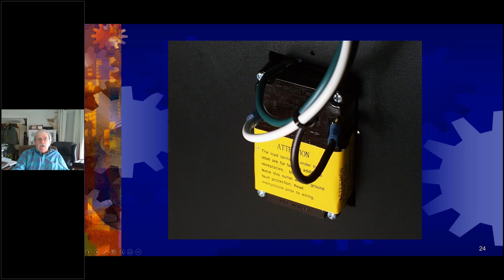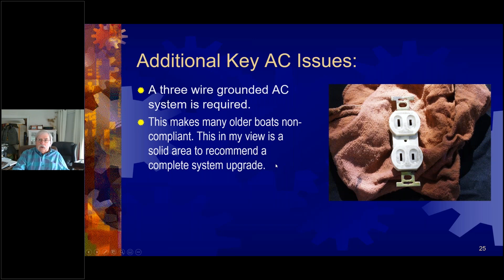Again, in surveys of older boats, this is an inland thing. Up around the Great Lakes you've got some really nice old boats still using a 2-wire AC system with no grounding. Personally, I think it's a good recommendation that those boats get updated. They're no longer compliant, and it's a legitimate recommendation to upgrade to a 3-wire system to help mitigate electrical shock for personnel.